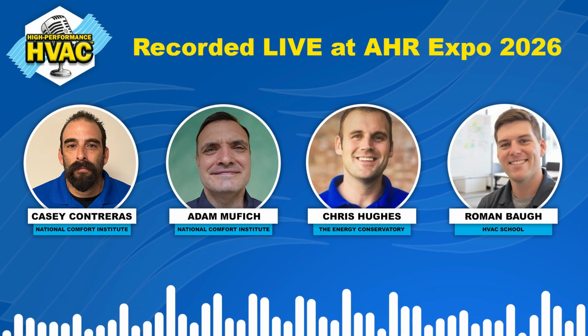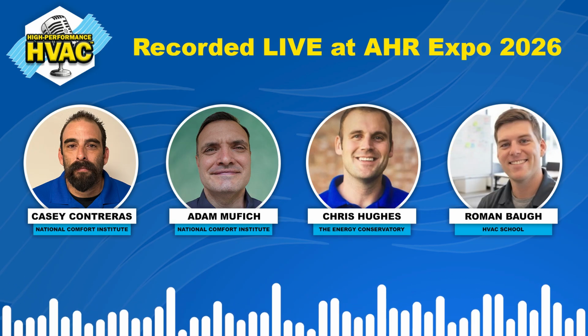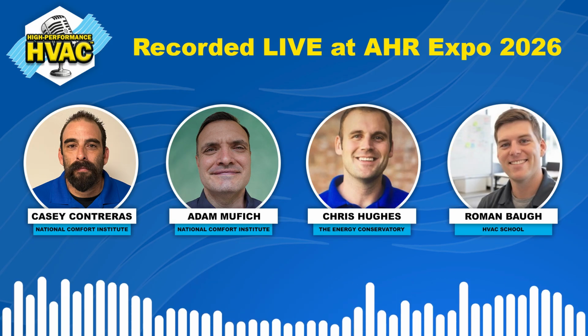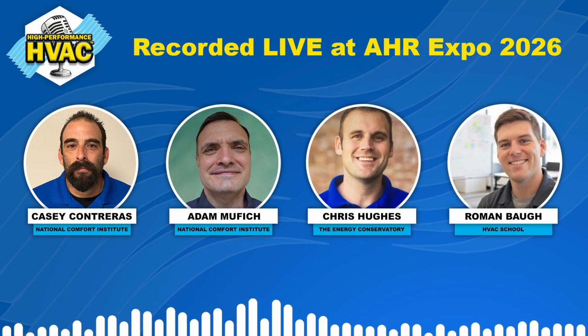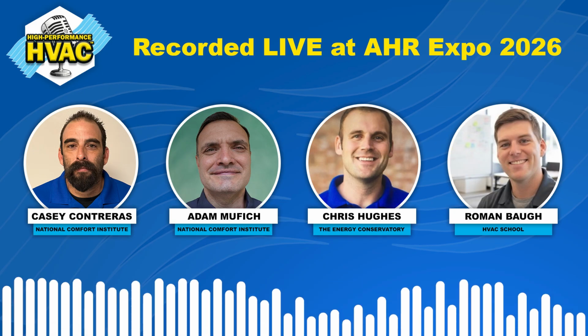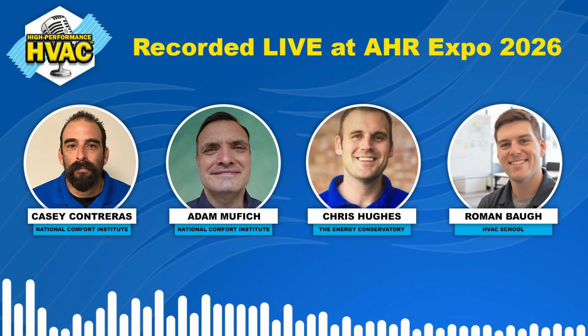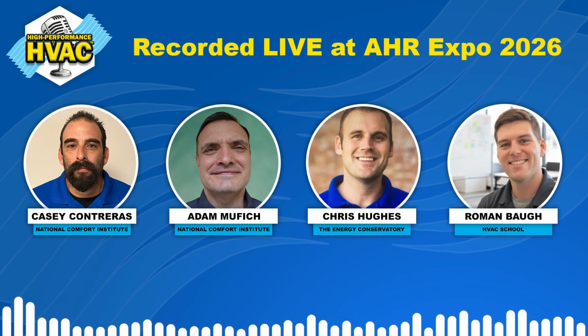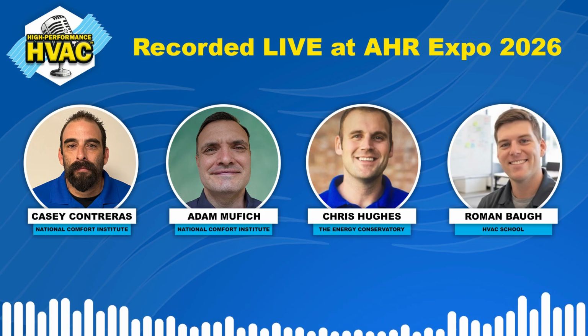And so it's sitting there chugging away as fast as it can go, and it still can't create high enough head pressure, right? Because remember, head pressure converted to saturation temperature can't create a high enough condensing saturation temperature to meet target, and so it wasn't hitting targets, and then suction pressure dropped.